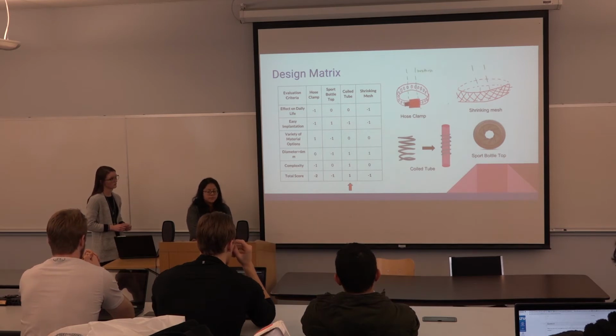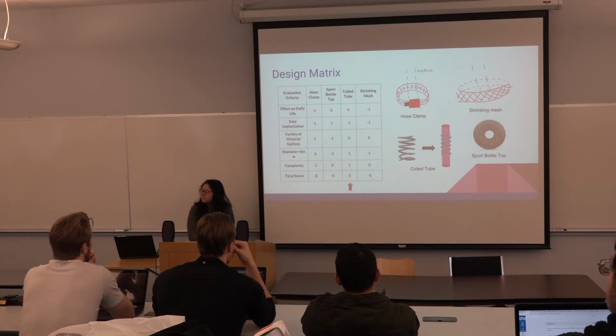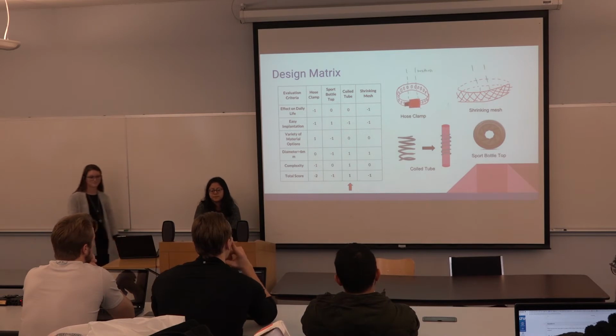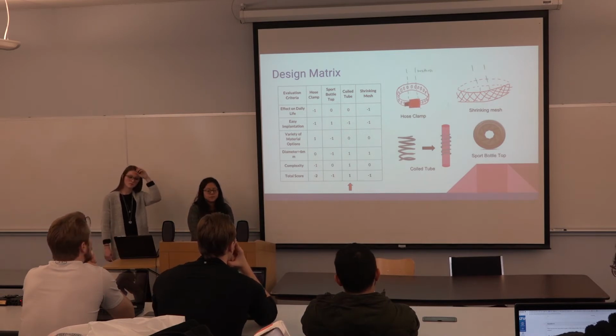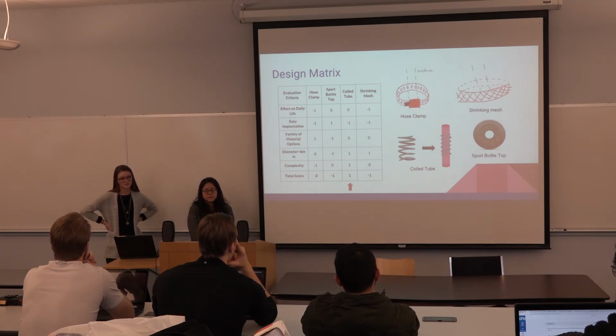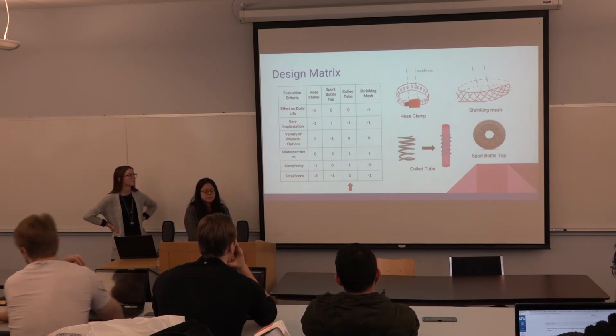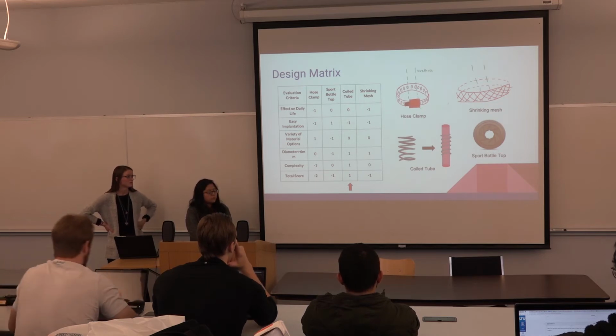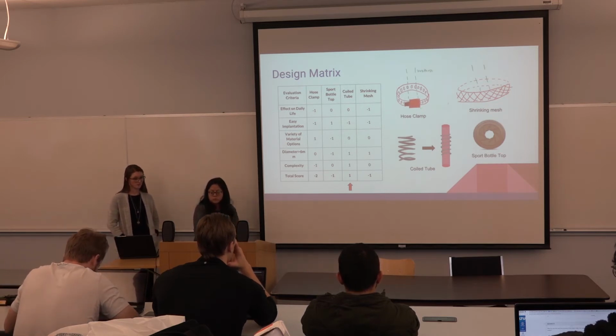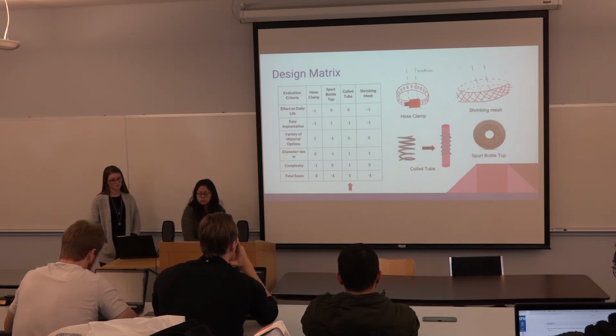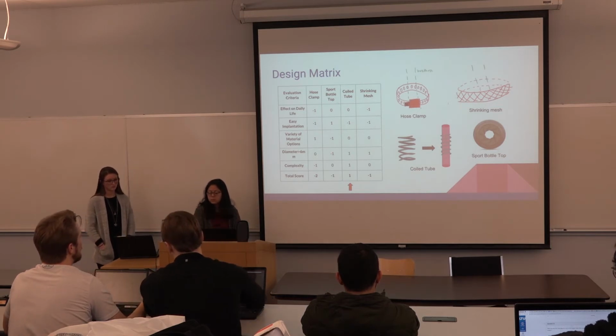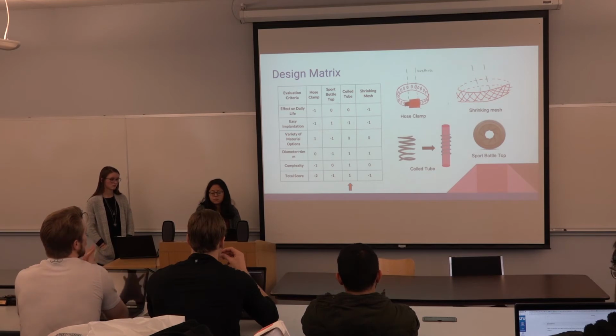With these objectives and constraints in mind, we have designed a tube-like cuff to coil around the outside of the urethra. This design was most favorable when evaluated against our criteria, mainly because its coiled shape is designed to spread out the constriction forces across the entire length of the urethra. This will decrease pressure and atrophy of the urethra and therefore lower the patient's pain. This design is also easily implanted through the vaginal wall because the predetermined curve allows it to be wound into place around the length of the urethra.